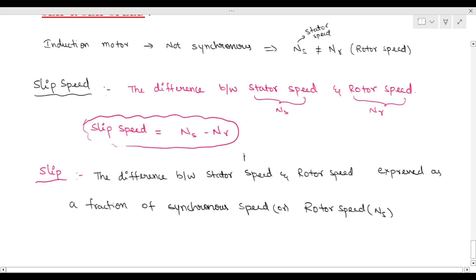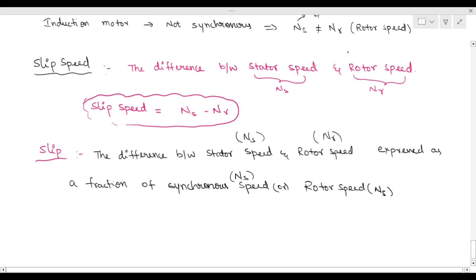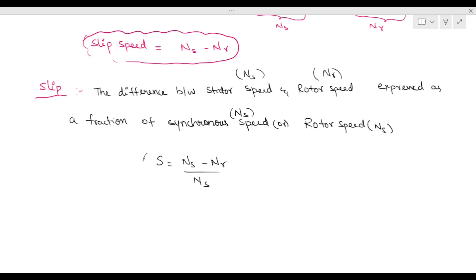The difference between stator speed ns and rotor speed nr, expressed as a fraction of synchronous speed. Slip can be written as: s equal to ns minus nr by ns. This is the formula for slip.